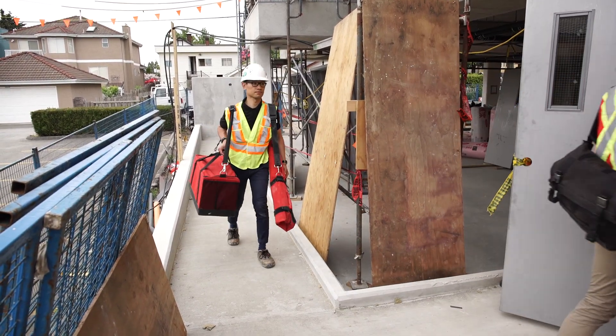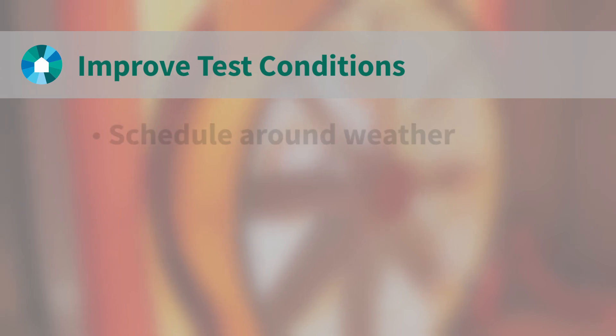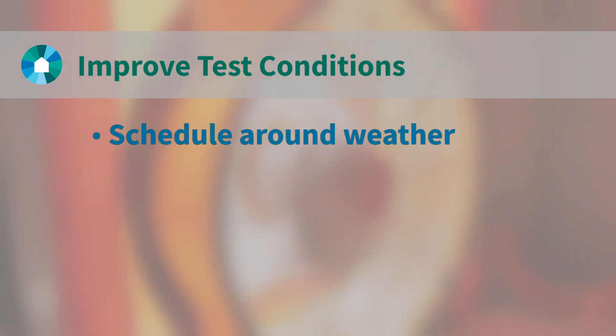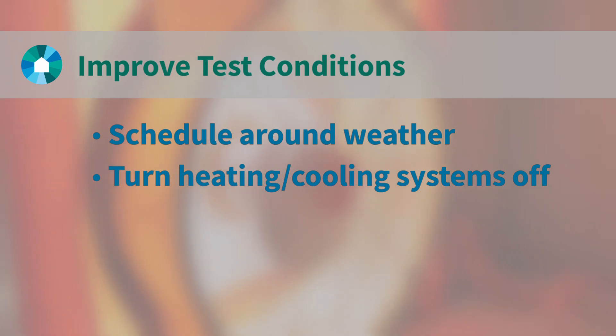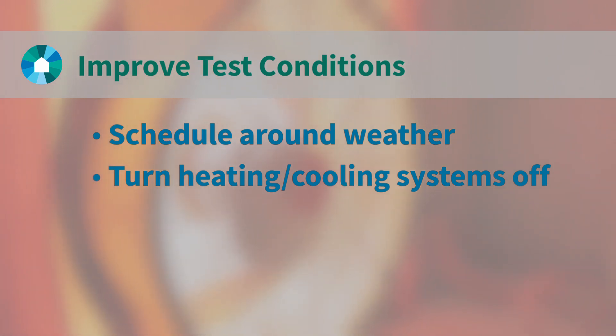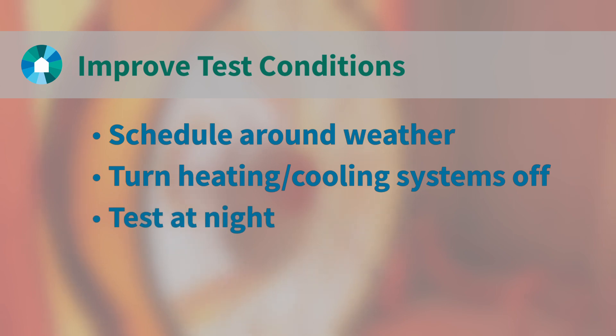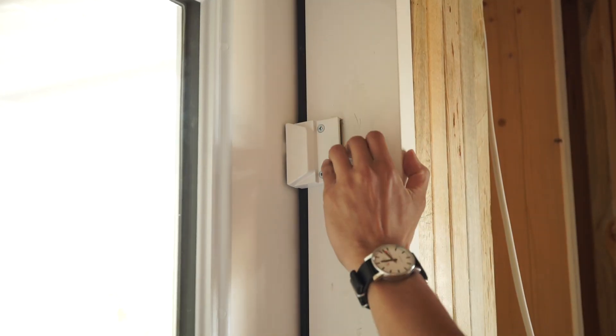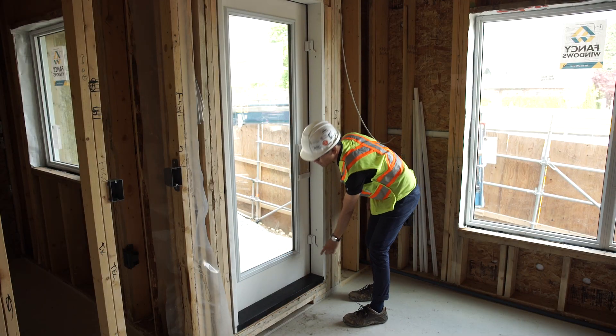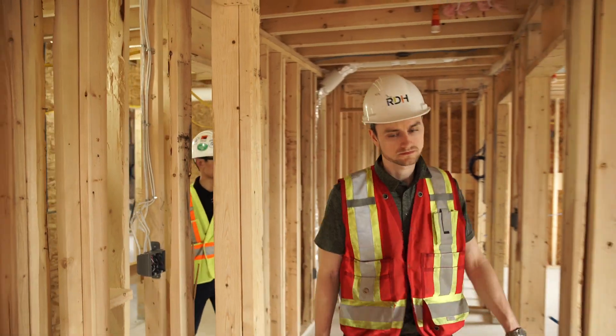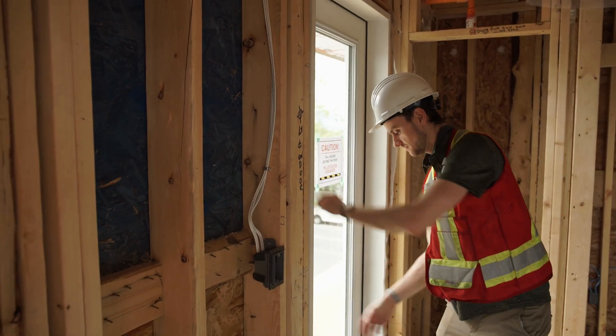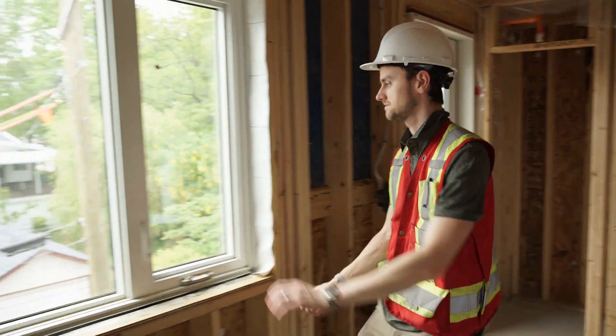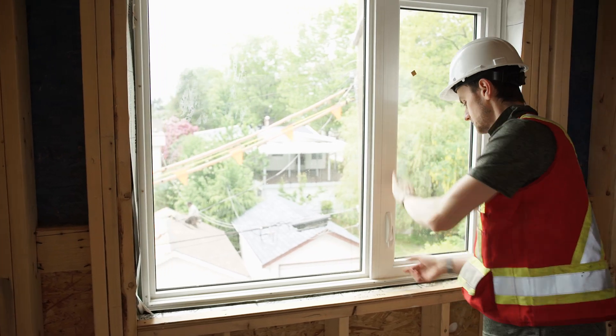Leading up to and during test day, the weather forecast should be tracked to confirm that temperature and wind conditions will be suitable. For large buildings, ensure the building isn't significantly heated or cooled compared to the outdoors, and consider testing at night when weather is stabilized. All exterior doors and windows must be closed and locked during testing. Complete a building walkthrough prior to running the quantitative test to check this, as one open window or door during the test, even for a second, can impact the test results.